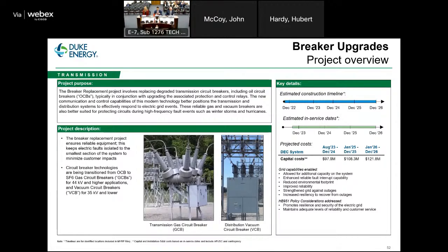The current, I'll say the legacy technology on the transmission grid is called an oil circuit breaker. It's really an oil-filled tank. That oil actually interrupts the arc that's created when that high energy breaker operates. Of course, these are from 44 kV on the transmission side up to 500 kV, and then also the distribution class circuit breakers in our substations as well. So 24 kV, 13 kV, those are also included under this program.